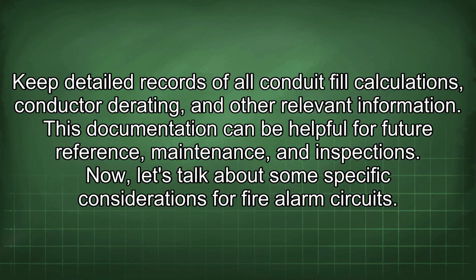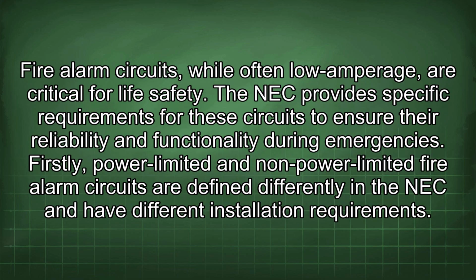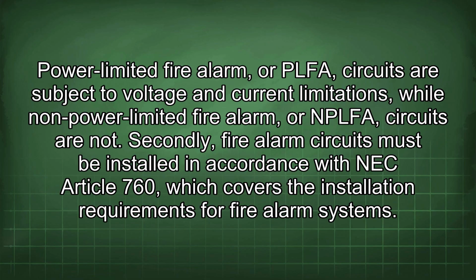Now, let's talk about some specific considerations for fire alarm circuits. Fire alarm circuits, while often low amperage, are critical for life safety. The NEC provides specific requirements for these circuits to ensure their reliability and functionality during emergencies. Firstly, power-limited and non-power-limited fire alarm circuits are defined differently in the NEC and have different installation requirements. Power-limited fire alarm, or PLFA, circuits are subject to voltage and current limitations, while non-power-limited fire alarm, or NPLFA, circuits are not.